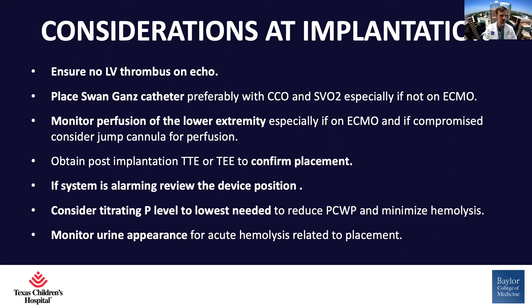We should consider titrating the P level to the lowest level that's needed, and I'll explain in a second what that means, as we want to reduce wedge pressures and also minimize hemolysis. Just running the device at the highest level doesn't necessarily mean that it will provide you with the best decompression. You might be able to achieve that with the lowest, certainly lower, support levels. And obviously, because of the higher risk of hemolysis with this device, we monitor urine appearance very closely for any type of acute hemolysis related to the placement of the device.